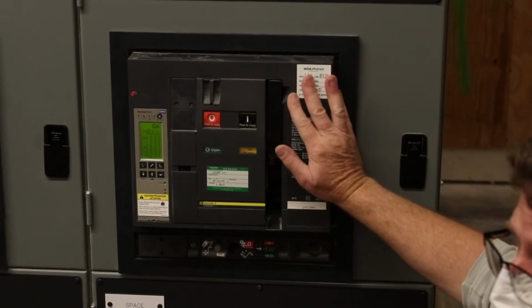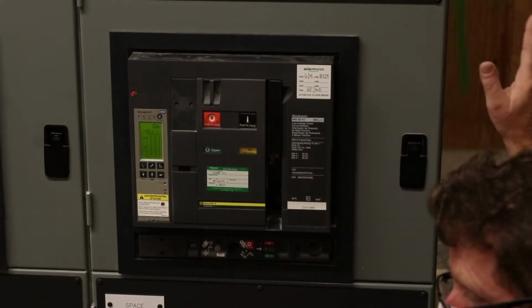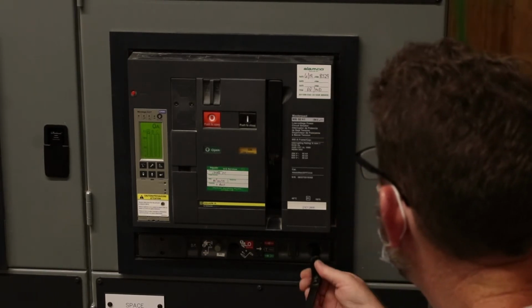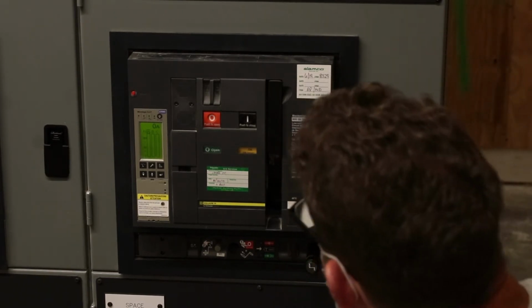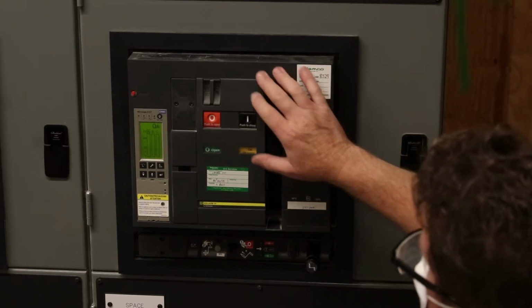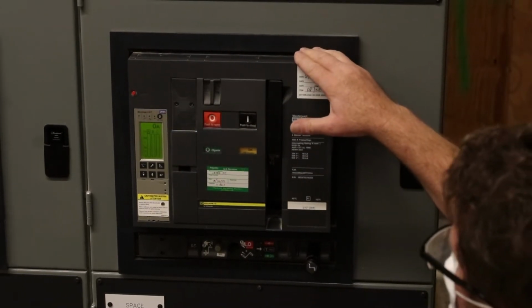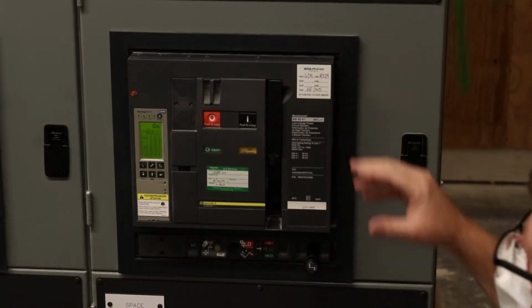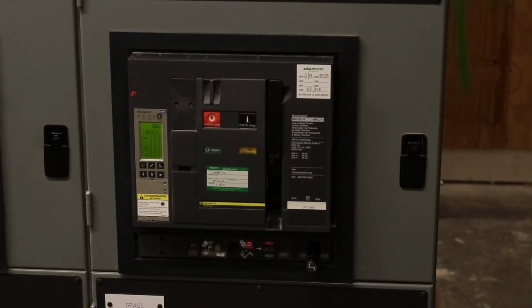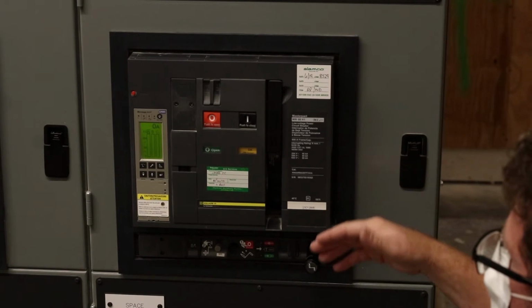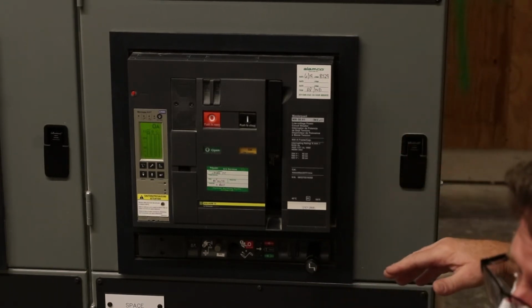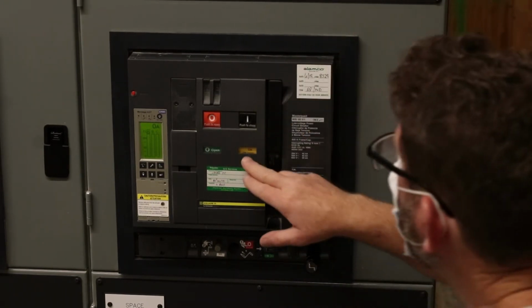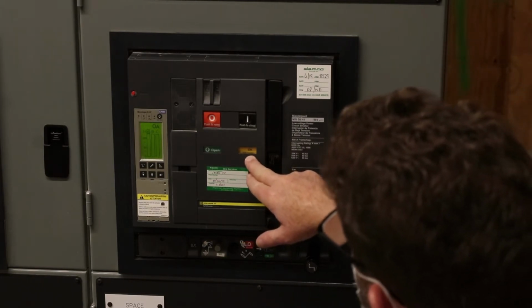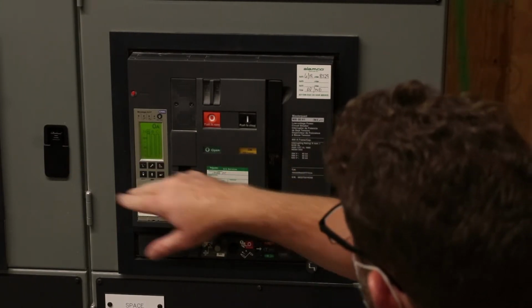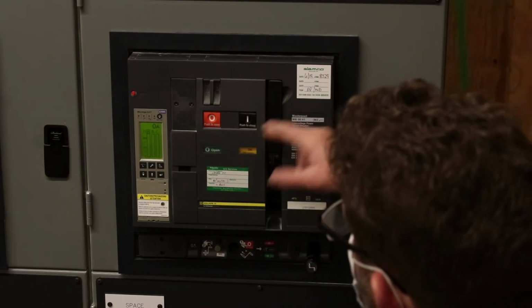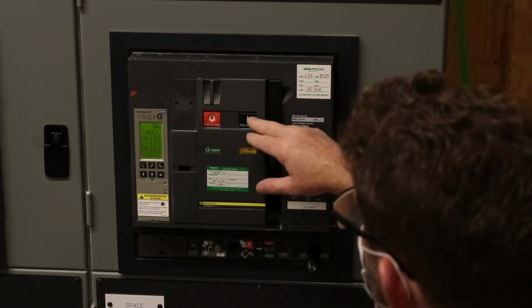I'm not going to rack this into the connected position because the bus is live. We're not geared up for that. But that's racking out into the test position. In the test position, like I said, the control connections are made up on the top. The 480 connections in the back are not made up. So when I open and close this breaker, we're not doing anything to the 480 side. Notice I showed you here the flag there. This is when it's okay. So right now, if you push this button, it's going to close.